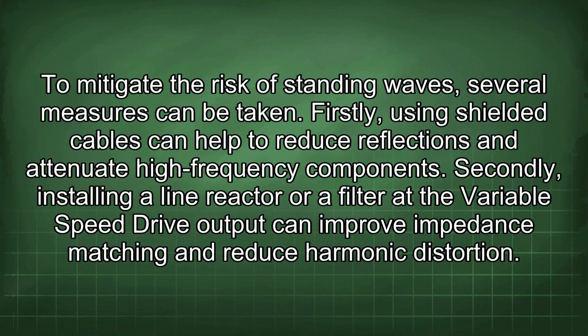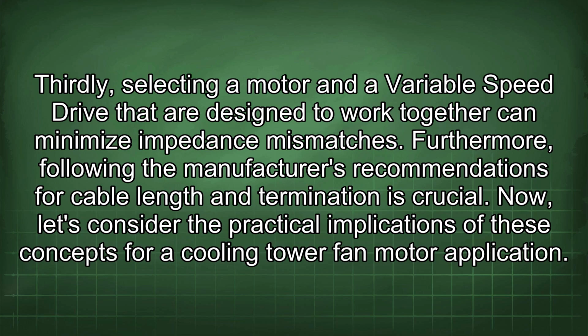To mitigate the risk of standing waves, several measures can be taken. Firstly, using shielded cables can help to reduce reflections and attenuate high-frequency components. Secondly, installing a line reactor or a filter at the variable speed drive output can improve impedance matching and reduce harmonic distortion. Thirdly, selecting a motor and a variable speed drive that are designed to work together can minimize impedance mismatches. Furthermore, following the manufacturer's recommendations for cable length and termination is crucial.